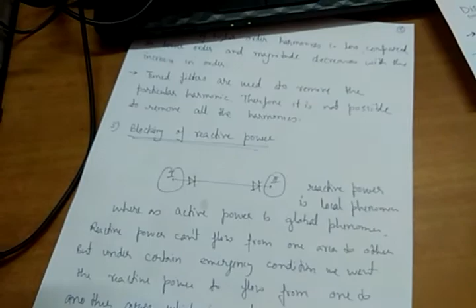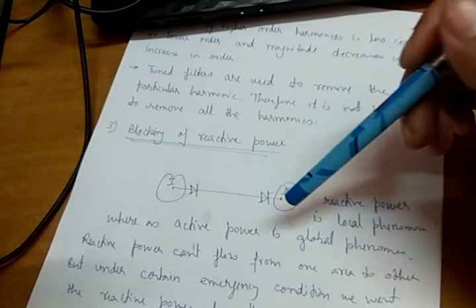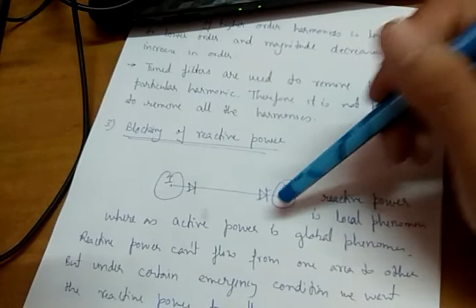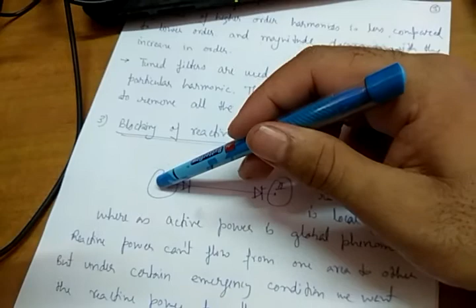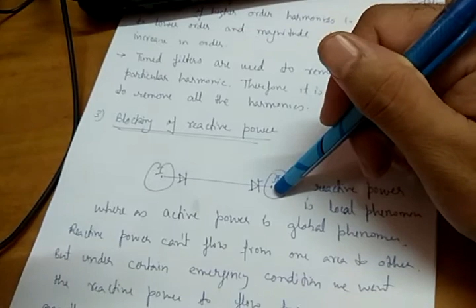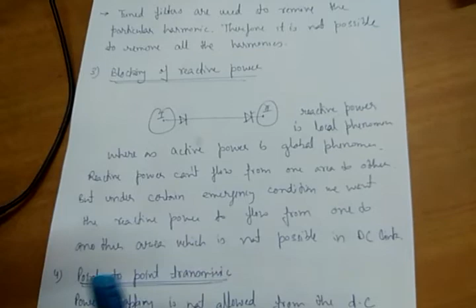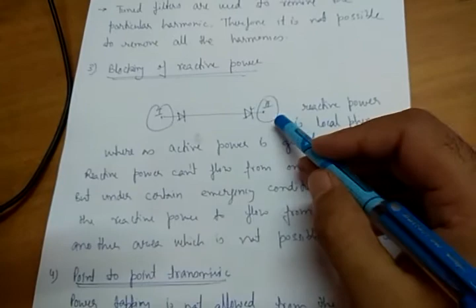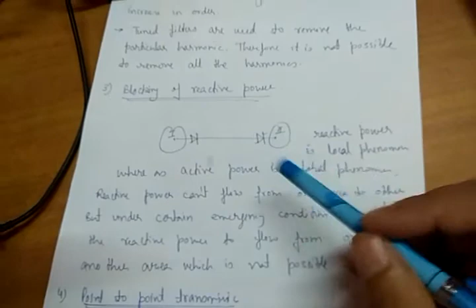So reactive power cannot flow from one area to another area in case of an HVDC system. We may need reactive power at this point, but this HVDC system is not able to supply reactive power from this point to this point. Maybe there is a voltage sag, so at that time we need reactive power here, and maybe there is surplus reactive power there, but this power cannot flow through this HVDC link. So this is the disadvantage of the system. Even if reactive power is required in a particular area during an emergency condition, it cannot be transferred through the HVDC link. For that we have to use some compensating device in this area. So blocking of the reactive power is another problem.